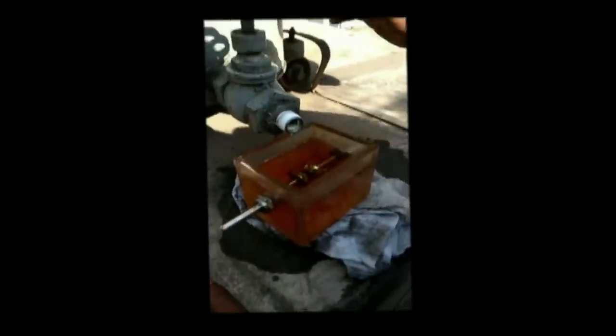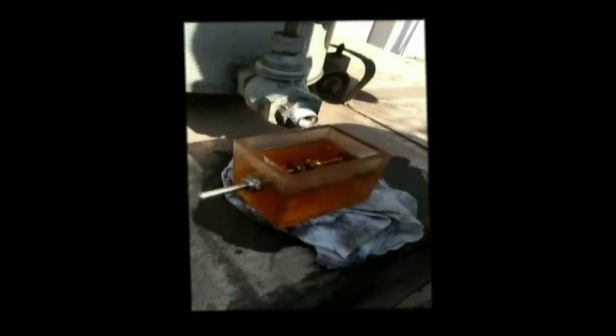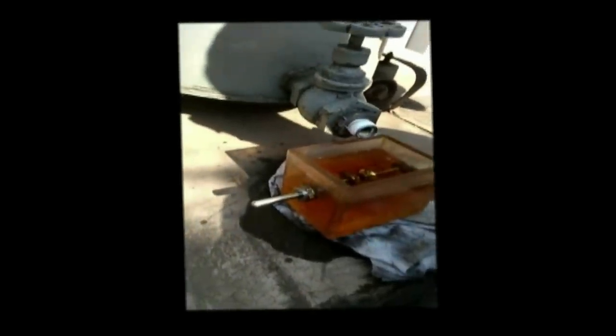Now we are doing the testing of the transformer oil BDV. This transformer oil sample is taken from the sampling cup, and this testing is carried out before the filtration of the transformer oil. Now watch in this video the step-by-step BDV testing procedure of the transformer oil.